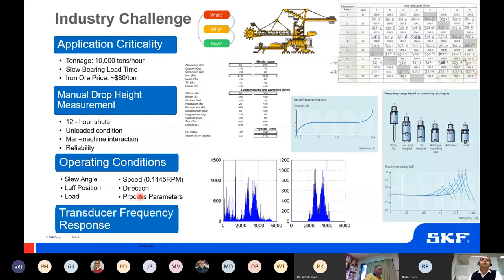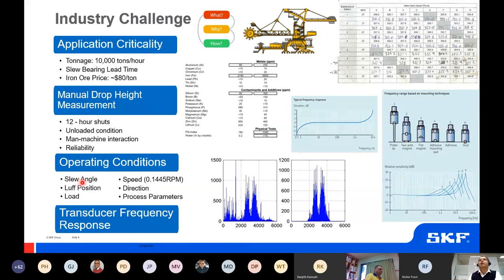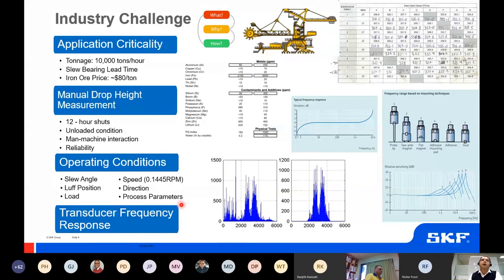The impact of operating conditions should be managed. I'm using the word 'managed' because we cannot simply say collect data only when slew angle is 30 degrees, luff position is two degrees, load is 700 kilonewtons, and so on. There needs to be a data analytics component involved so we can optimize predictability by collecting data in conjunction with the operating conditions.